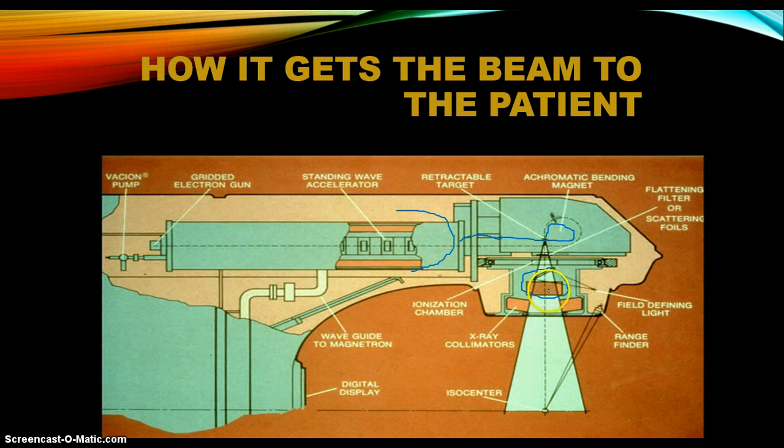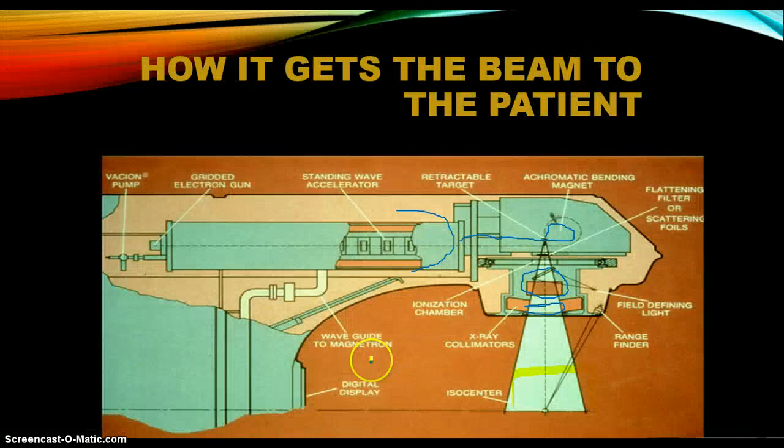And then the X-ray hits this right here called a multi-leaf collimator, and this resizes the X-ray to fit the shape and size of the cancer tumor. The X-rays are now done, and they will strike the patient, which will usually be right here on a table, waiting for his treatment. This is my little makeshift person, stick figure.